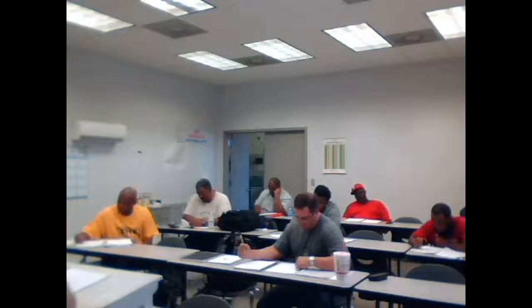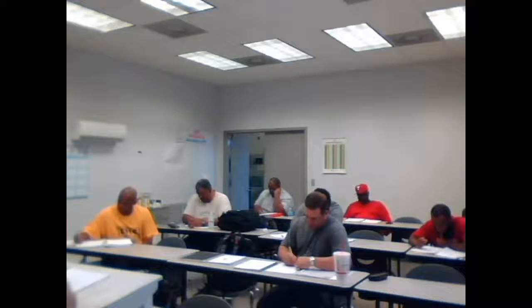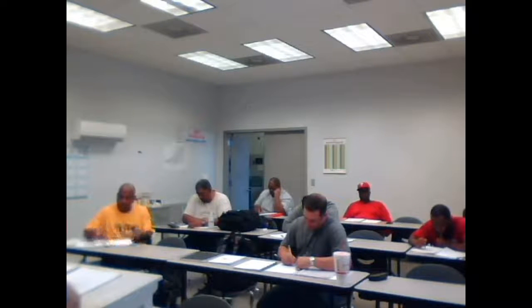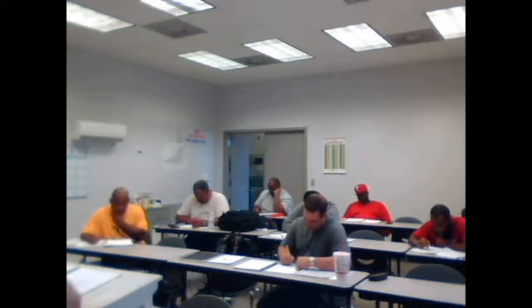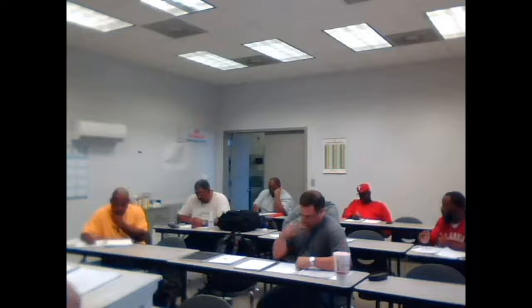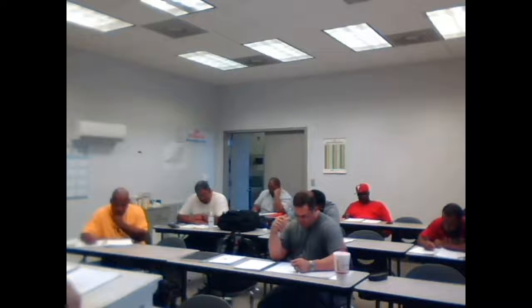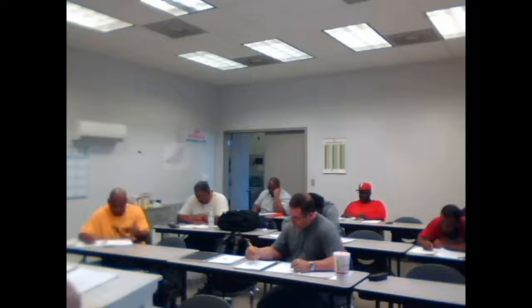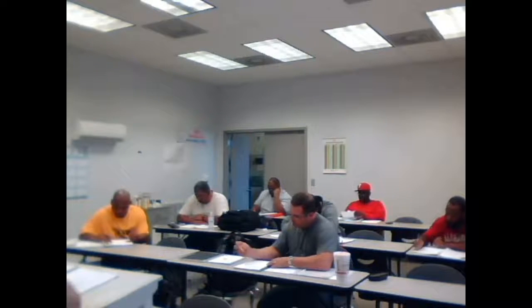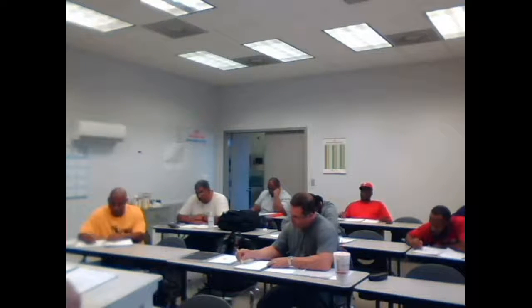So, let's start. Number 1, reading voltage from L1 to L2. I know some of you haven't dealt with 3-phase. What should I read if the system is in normal operating mode? 240. That's right. 2. Across the coil on branch 11, the coil is labeled C. Do y'all see that? What would we expect to read there the way it is? 24 volts. 24 volts, absolutely.